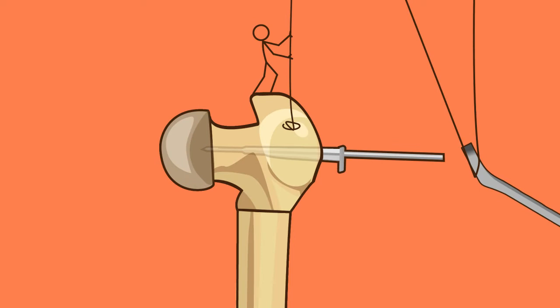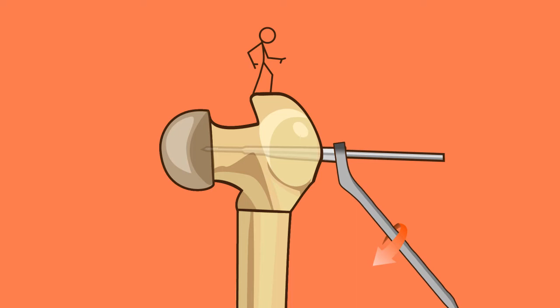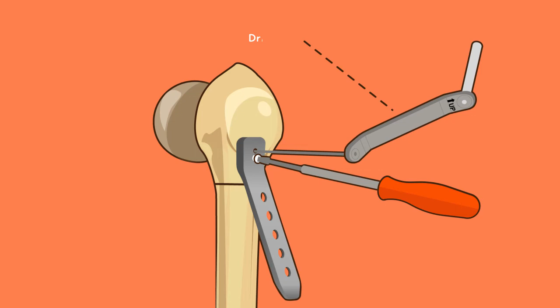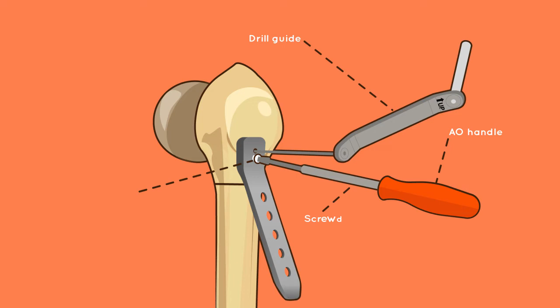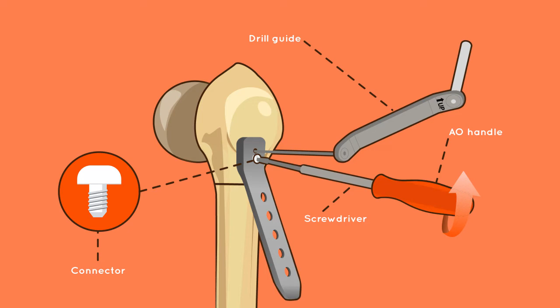Step 8. Plate assembly. Insert the plate through the incision and hook onto the blade. Ensure full contact between the blade and the plate at the connection section. The drill guides can be used over the guide wire to push the plate against the blade for maximum contact and ease the threading of the connector screw in the next step. Attach the AO handle to the screwdriver and lock the blade plate assembly by threading the connector clockwise through the plate into the blade as tightly as possible.